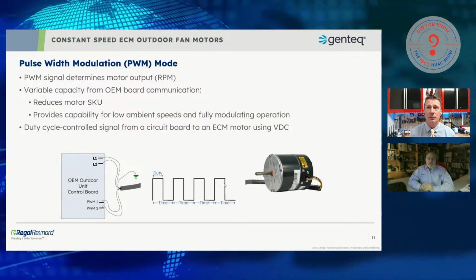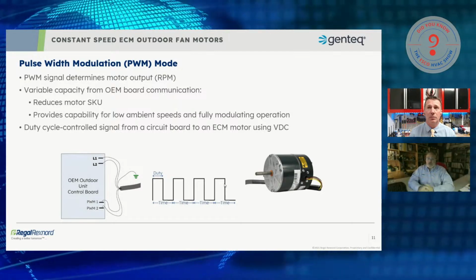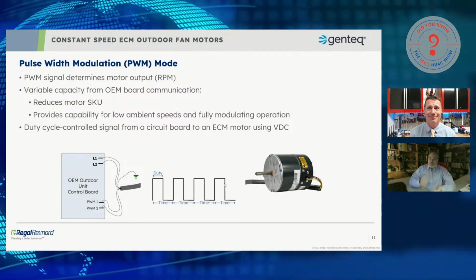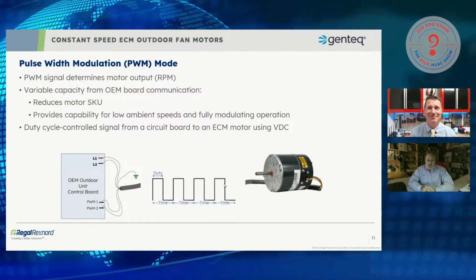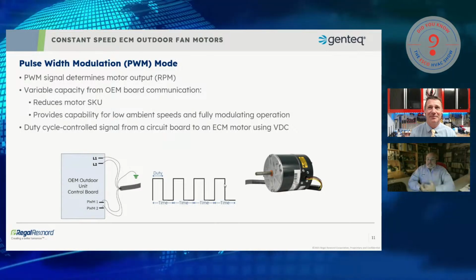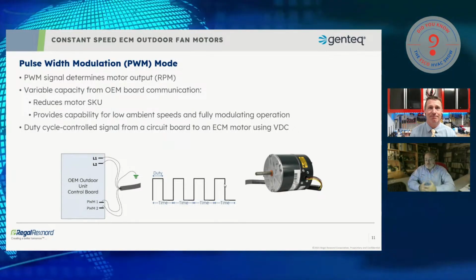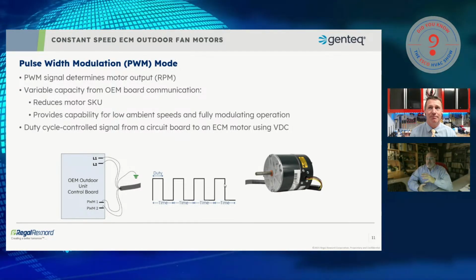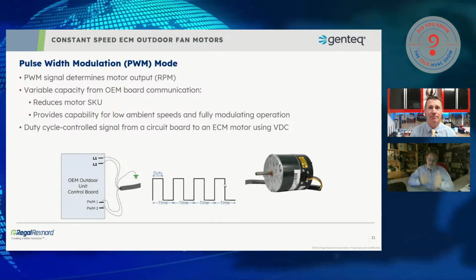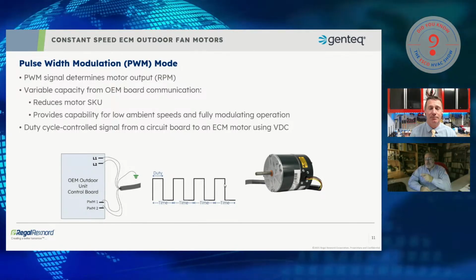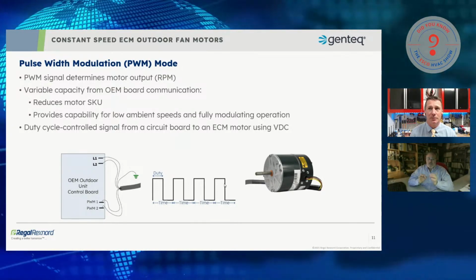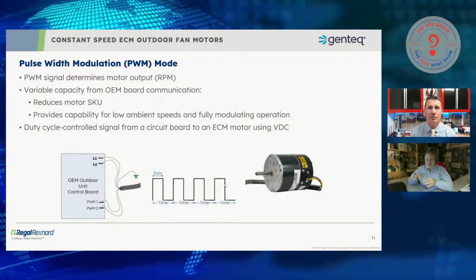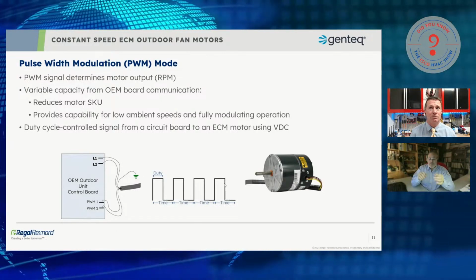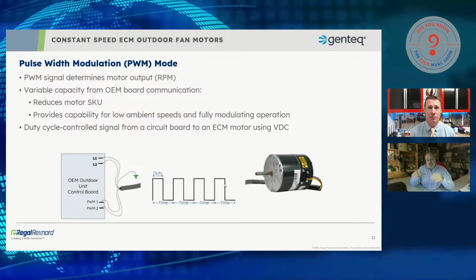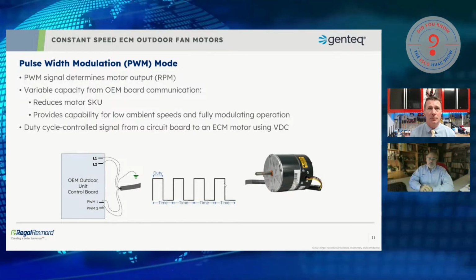While I was one of the first people to go out and buy an anemometer, and one of the first people to go out and buy a combustion analyzer, you don't necessarily need a meter capable of reading PWM today, because manufacturers are recognizing that most technicians don't have it. They're going to convert that to a DC voltage and say, if you see this DC voltage, the motor should be performing properly at first or second stage or low ambient.